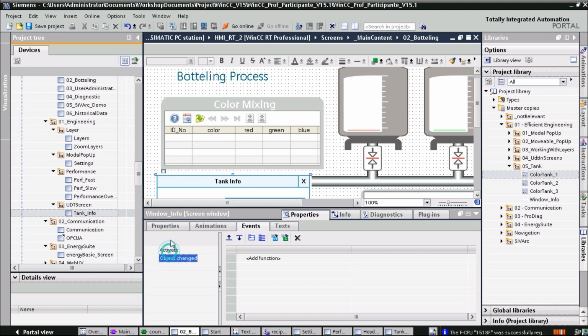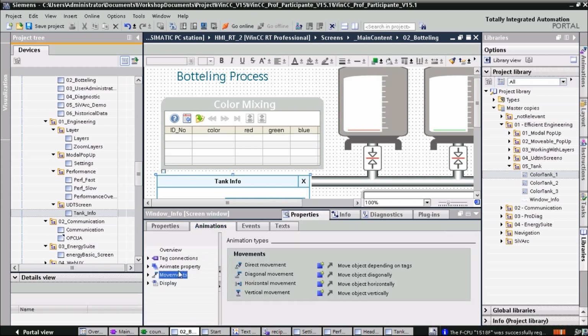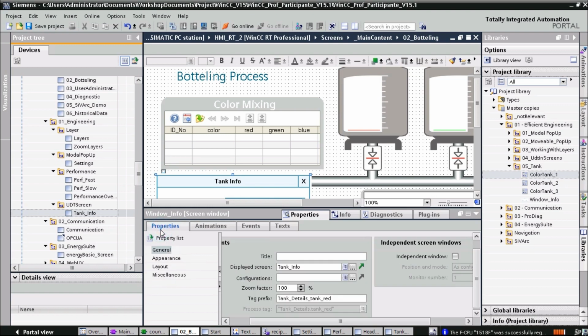And of course, I should be able to change the value in here. This one here doesn't move because I haven't connected it in the faceplate, but I see it's connected to the tag because this value changes as soon as I change the value here, because the I/O field is connected to the same tag.